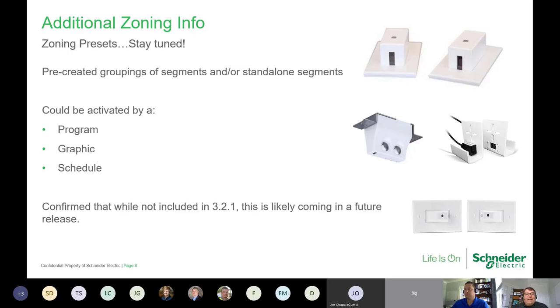And right now, because we didn't have our connected room solution at the time, they're using those Lutron sensors in our Nashville office to detect when our movable partitions are open versus when they're closed. So when they're open, the lighting control panels know to control adjacent spaces as one. When they're closed, they know to control them independently.